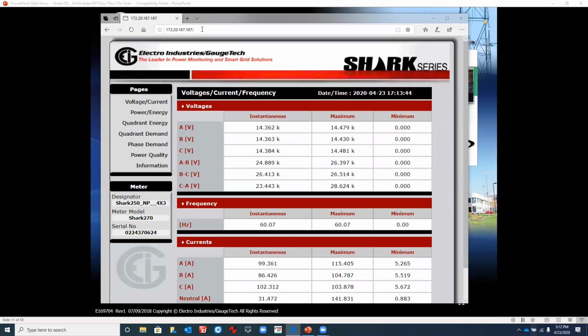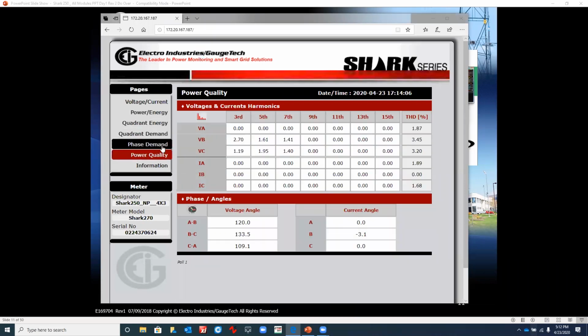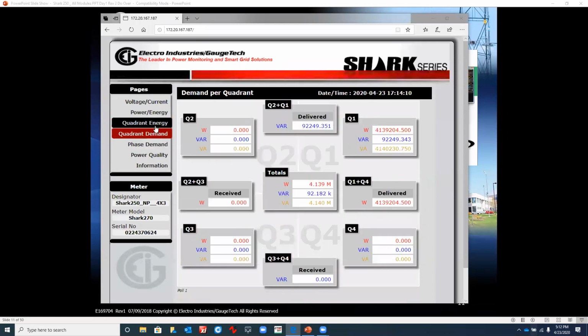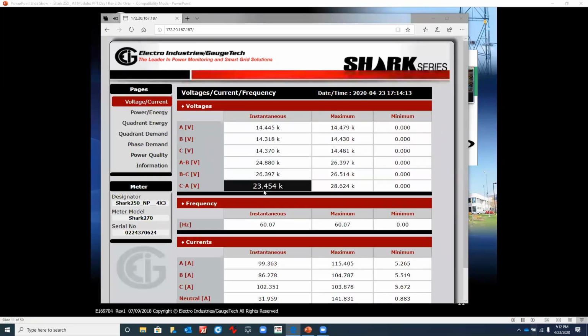It's very responsive. It's a good way to have a connection to the meter at your desk, as long as it's on the network and you have access to it, you can bring up all the information. It's a read-only screen. Basically, you can see all your voltage and current and phases and different things, power quality, all the different things that you would see if you were connected using the communicator software. So if someone wanted access to the meter on the network, you may want to just give them the IP address. Someone within your company that's allowed to do that, of course. But if you're on the same network, you should be able to enter the IP address and view that information.